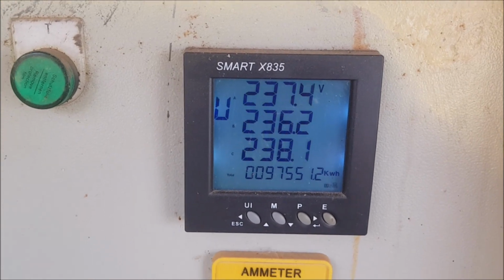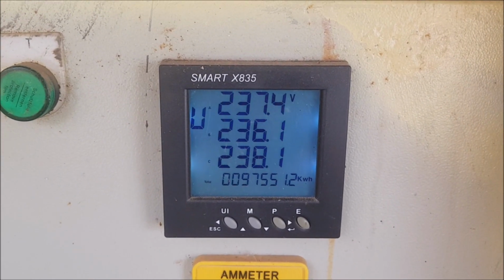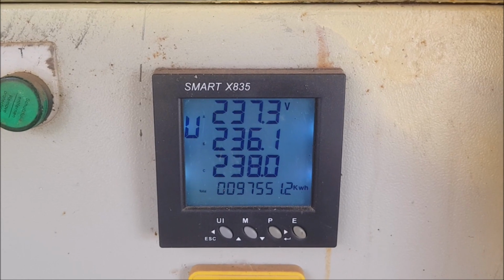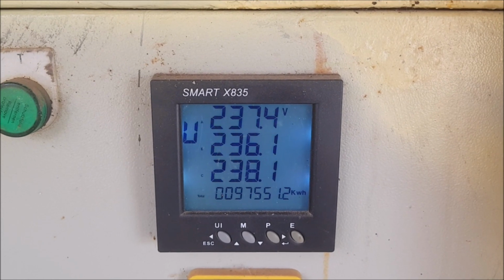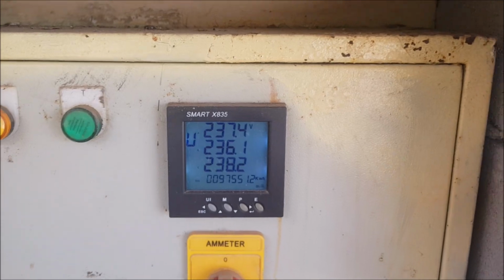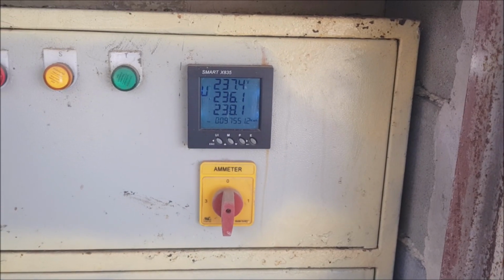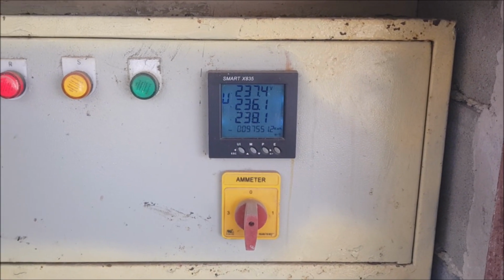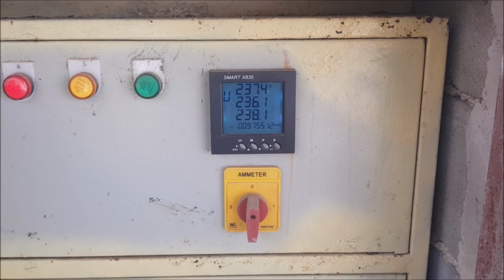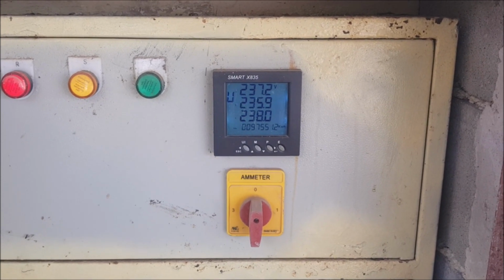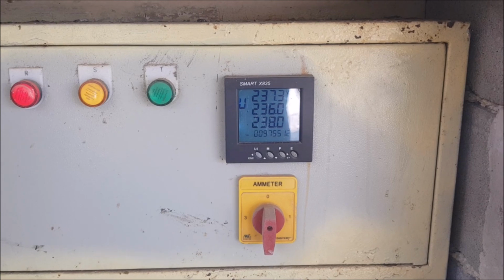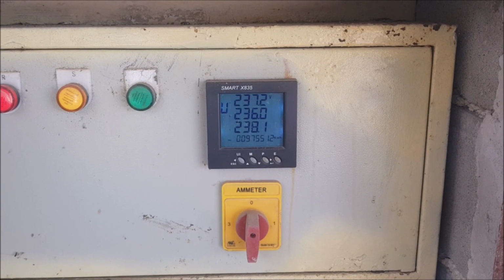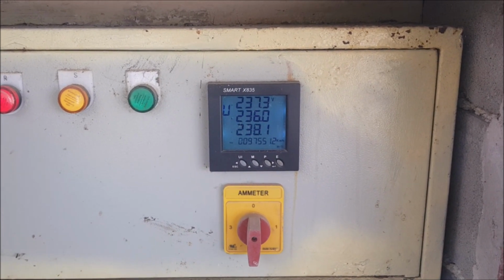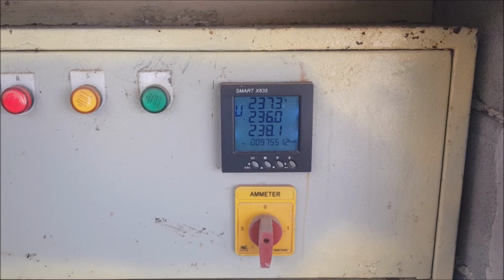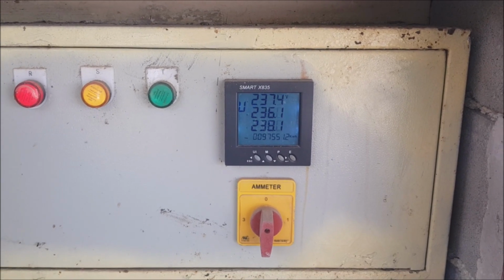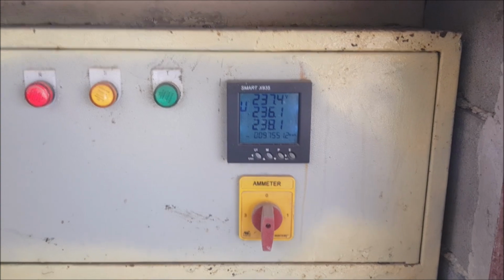This is even though I have quite thick wiring here, 16 square millimeter wiring from this point to the garage. But because of the long distance, around 100 meters, and the high loads—or in this case the strong feed-in from that point—the current is high, which also means the voltage drop will be higher at this point.